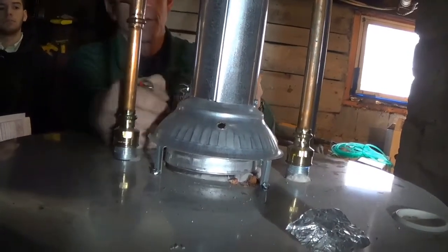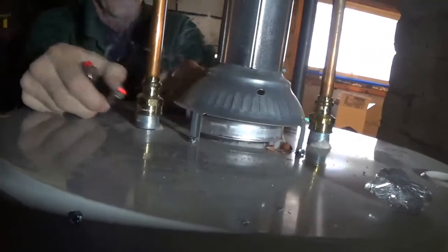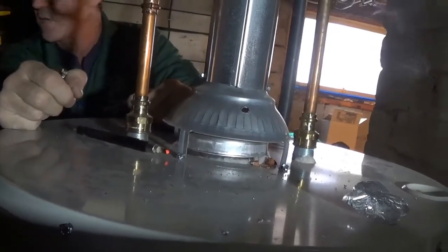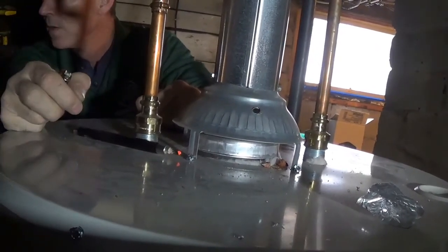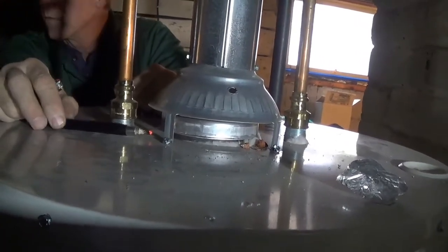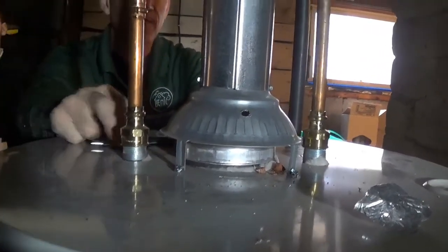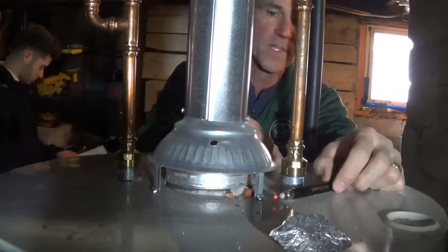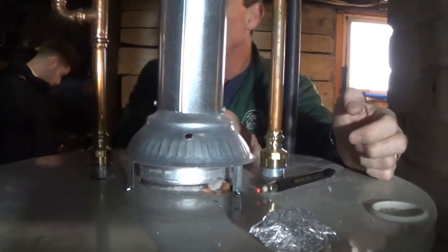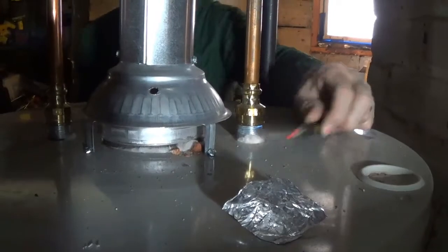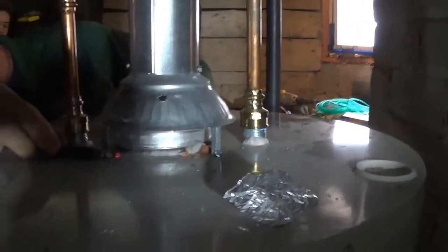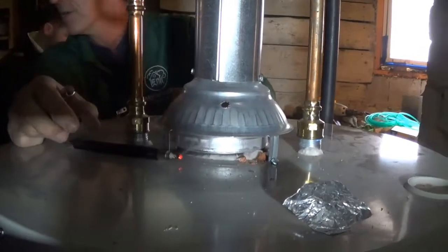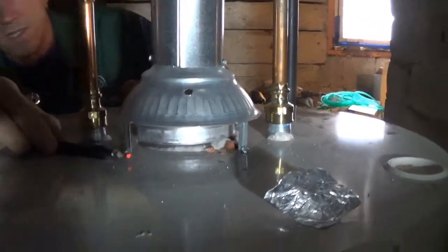I just put my hand here. I don't feel as much hot coming out at me, and this is definitely moving in the right direction. This was where it was at its worst before, and it's turning the corner the way I like right away. It's been about 5 seconds. It's getting sucked sideways all the way around. This is a passing spillage. See what I'm saying? I've got my smoke pencil out here and it's getting sucked in sideways. That's passing. When it's kind of making up its mind and you hold it right underneath and it's going back and forth, that's failing. If it's not definitely getting sucked in, it's failing. So this is good. This is passing under natural conditions with the heating system running.